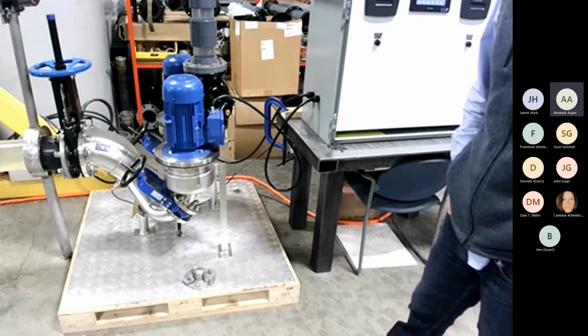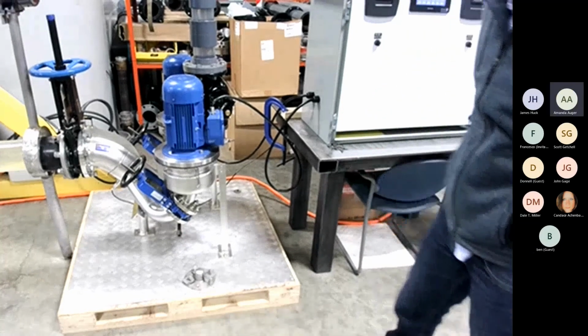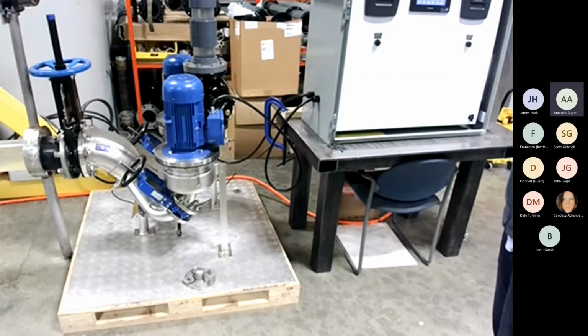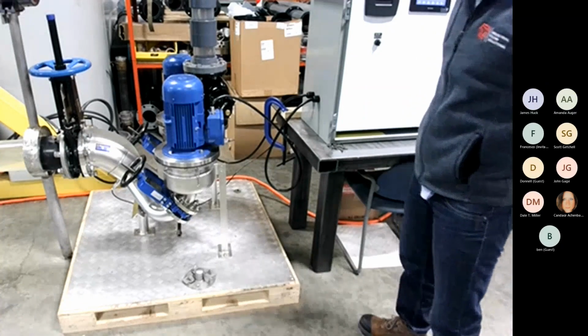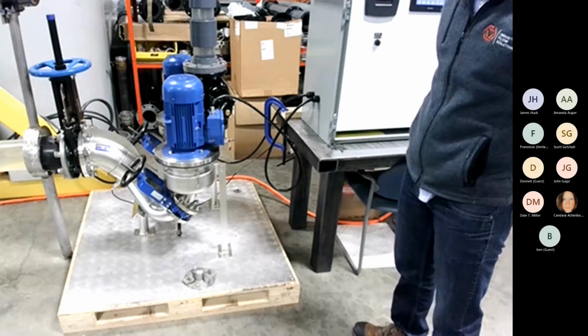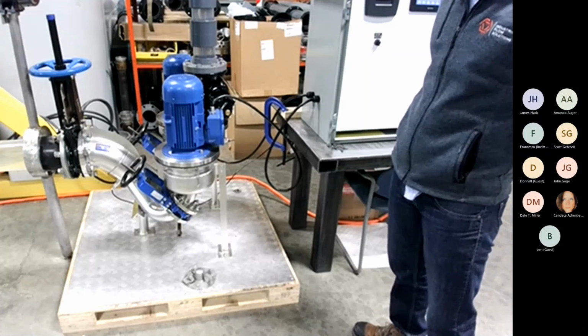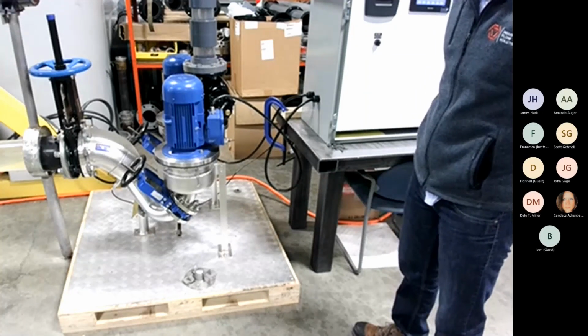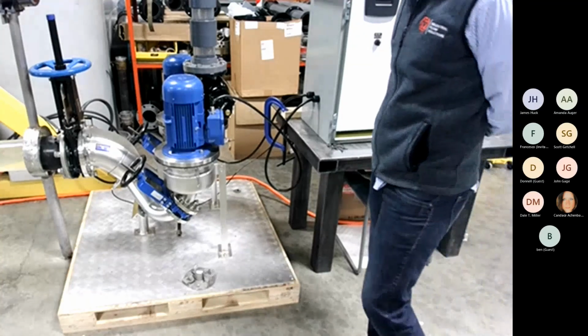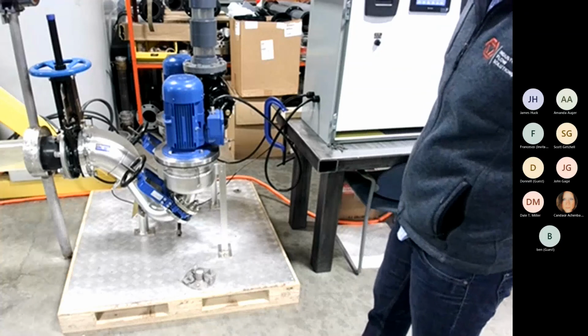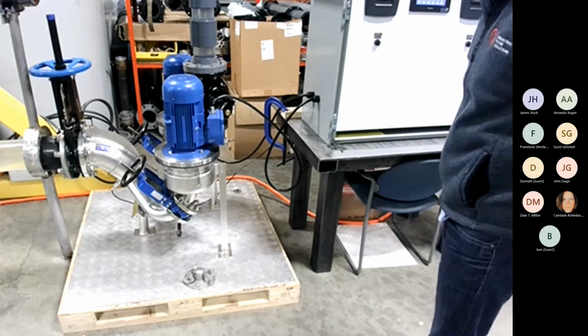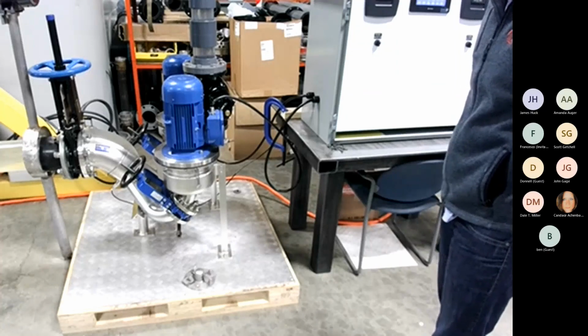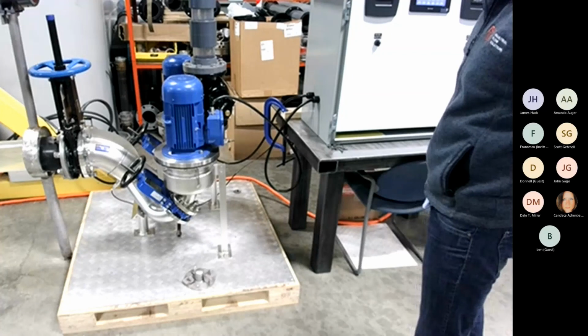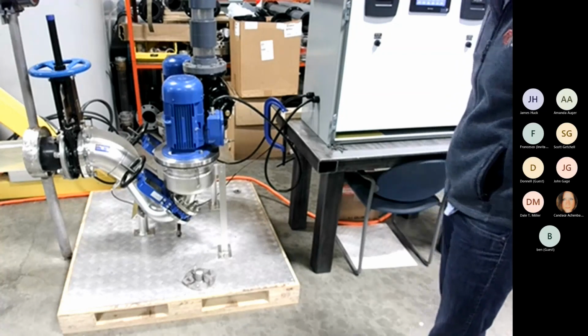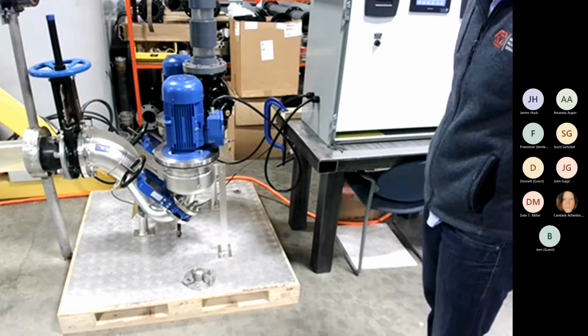Shouldn't be a lot of things. The last question: we see a high percentage of pump failures and maintenance due to FOG. How does the system help combat that? Good question - what's great about this technology is that it's a direct inline pump, so there's no opportunity for things to separate or coagulate. Fats, oils, and greases that come into the system are immediately ejected, rather than collecting and sticking to basin walls and caking up. It comes into the system and immediately goes out. So if you have high levels of fats, oils, and greases, this is really the technology that should be used for that environment.